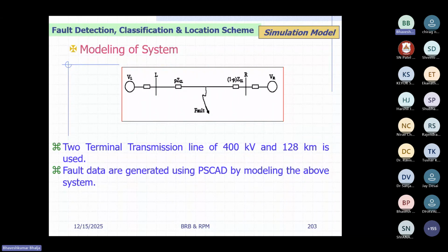If you have a line to line fault, let's say an RY, YB or BR fault, then the same applies. I told you about only one type of fault, RG. The same thing you can perform for YG, all 10 types of faults, except open conductor. Open conductor is a separate fault. It usually occurs at distribution level, so we do not bother about that. Sometimes it is known as a broken conductor fault also, but it usually occurs at distribution or 66 kV sub-transmission level.